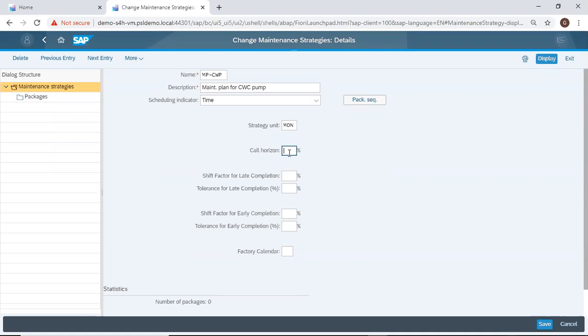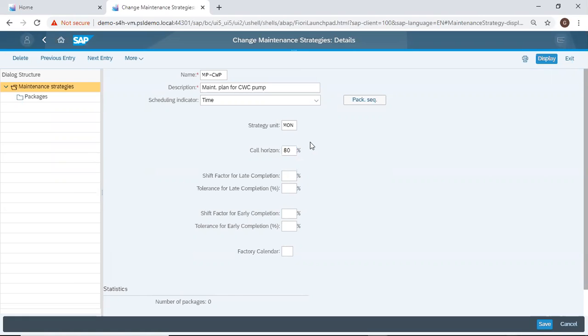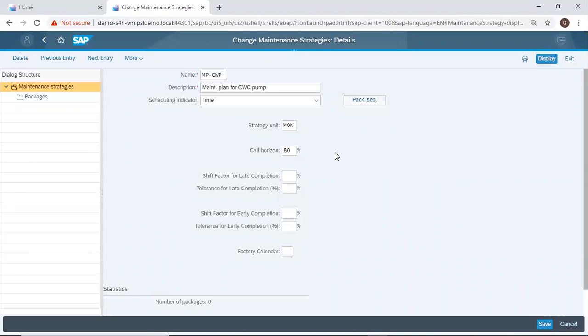Then I set my call horizon to 80%. This means, assuming we have 100 days, on the 80th day, the system will trigger my call object for the maintenance to be carried out on the 100th day. That's if I'm working with 100 day plan.